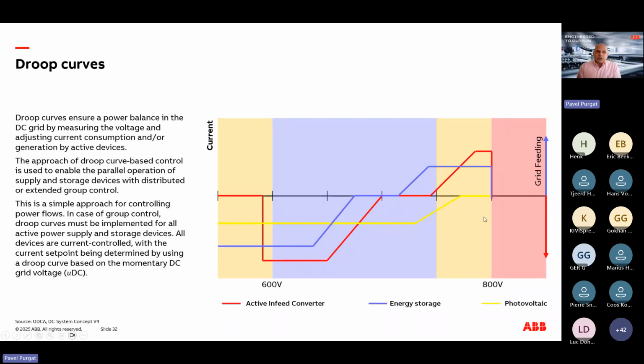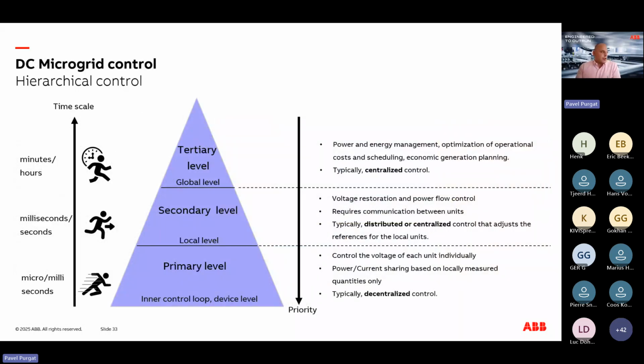So an important piece of the equation are the droop curves. But that's not all. The droop curves are usually provided on the very low level, or essentially in the converter, but it is not enough. We also need to think about the energy optimization, and that's why we also have tertiary level control, which is typically centralized, and this is where we do our energy management.